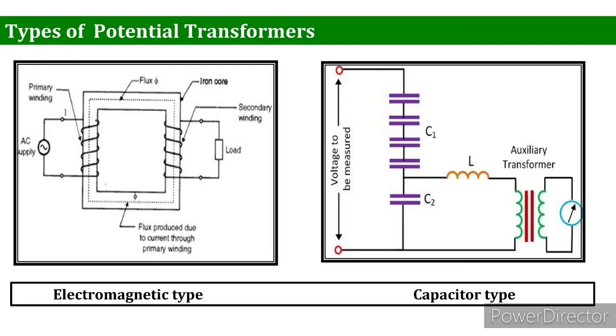The coupling capacitor type consists of a stack of series-connected capacitors made up of oil-impregnated paper and aluminium foil for the desired primary and secondary voltages. Primary and secondary terminals are connected across the capacitors. This is basically a capacitance voltage divider with a tuning inductance and an auxiliary transformer, as clearly shown in the figure. The primary portion consists of capacitors connected in series to split the primary voltage to convenient or desired values.